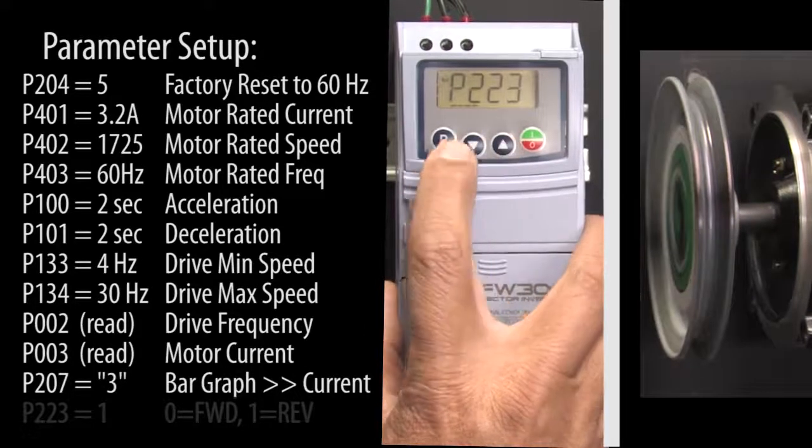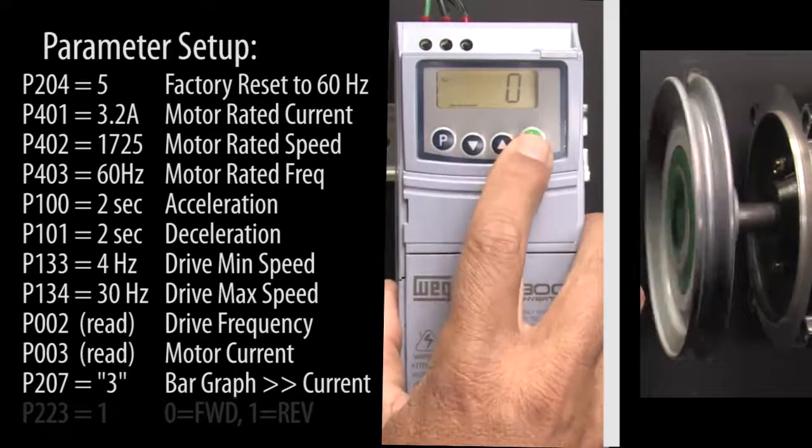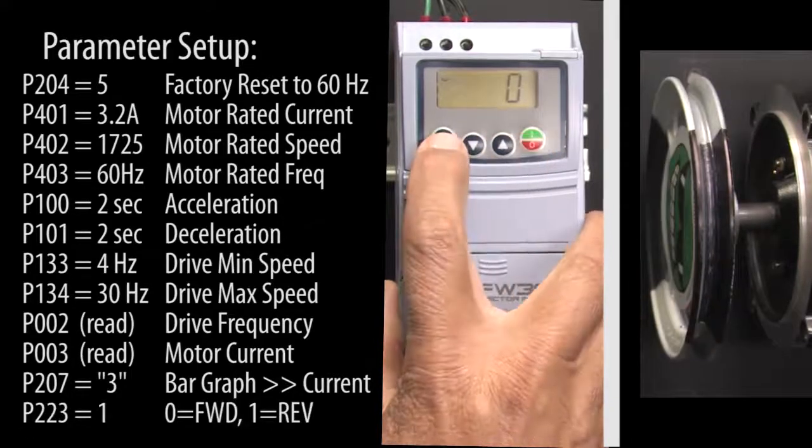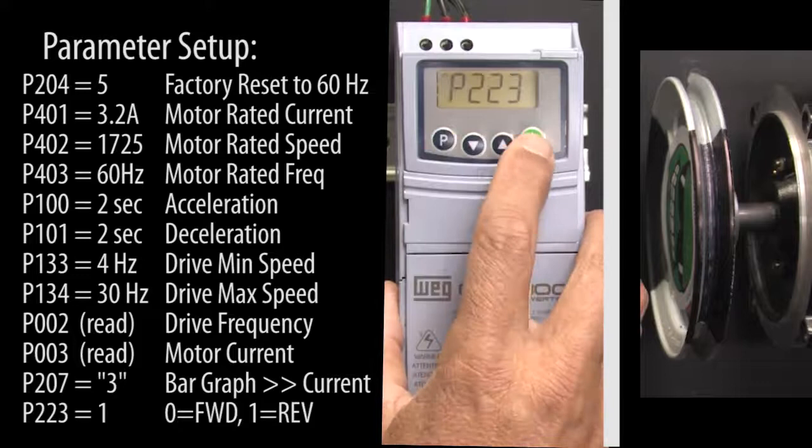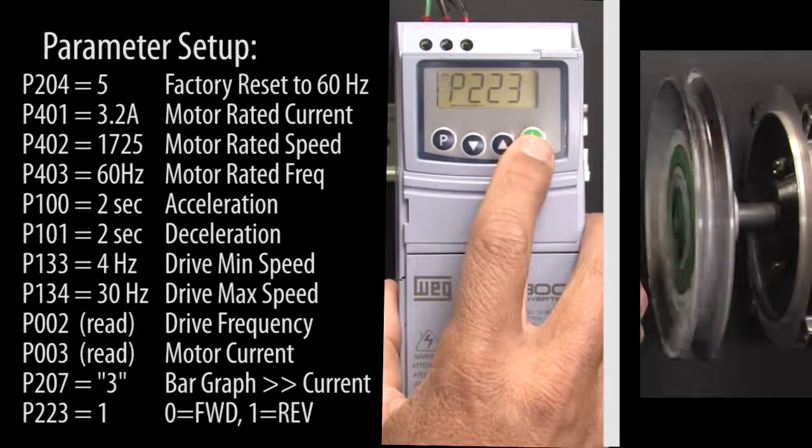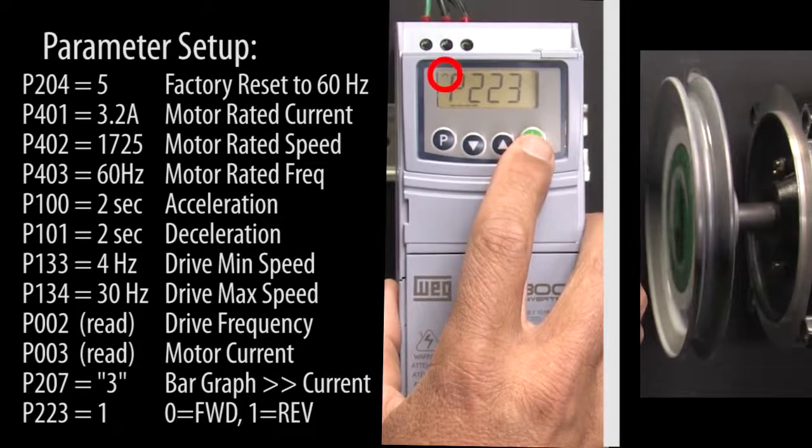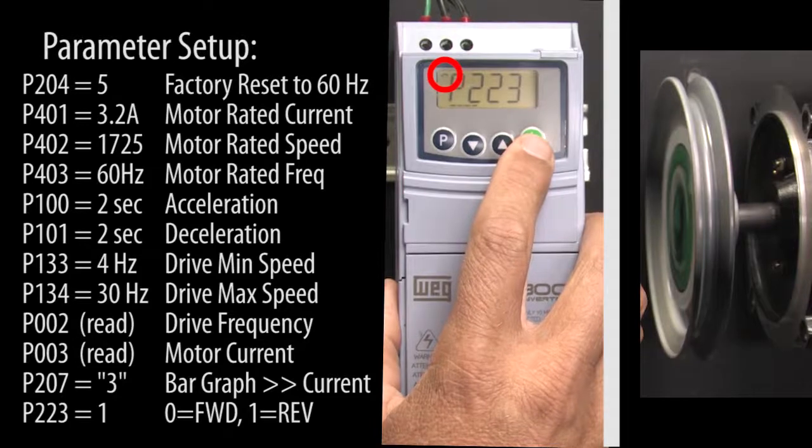Parameter 223 controls forward and reverse. Stop the motor. Change it to a 1. Hit P to accept that. And now when we run the motor, it rotates in the opposite direction and the rotation indicator up here also changes direction.